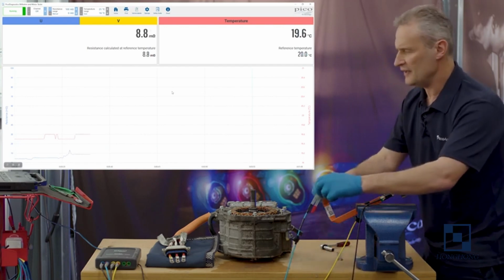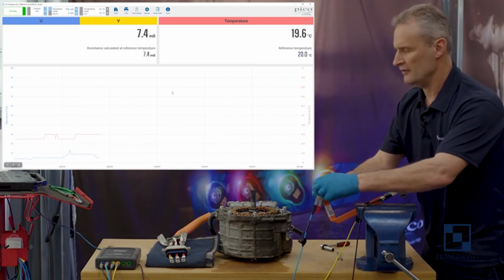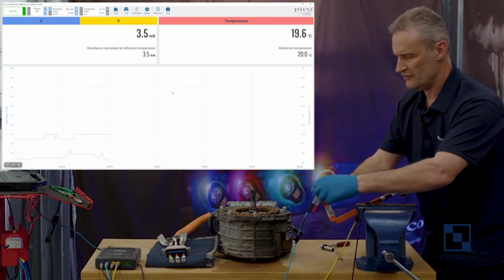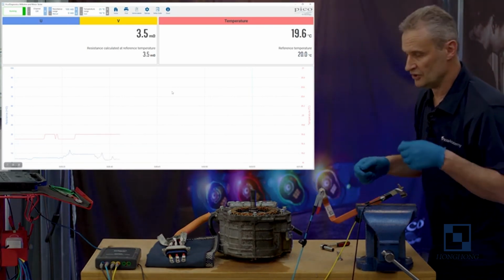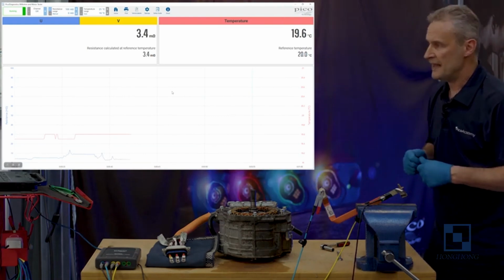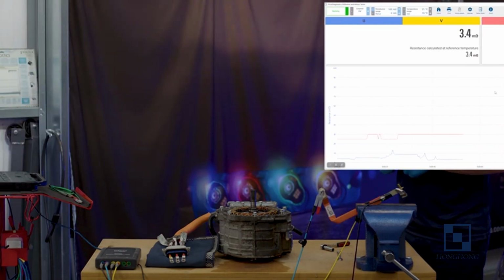So if you think about that, think about 100 amps passing through there. Amps times resistance equals voltage. That'll give us the voltage drop. So for 10 milliohms with 100 amps, we're looking at a 1 volt drop.